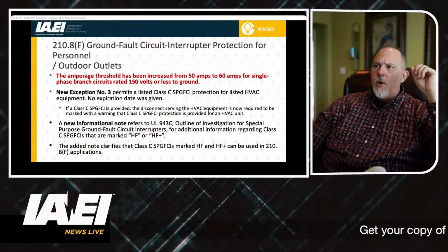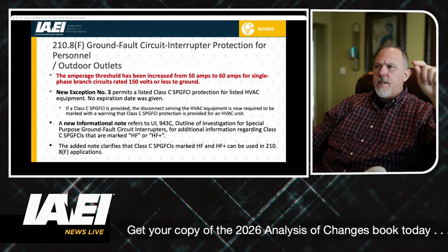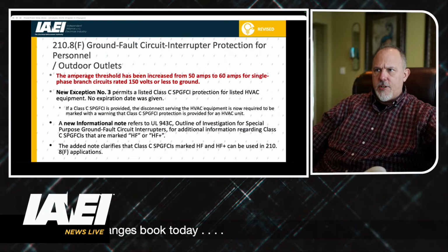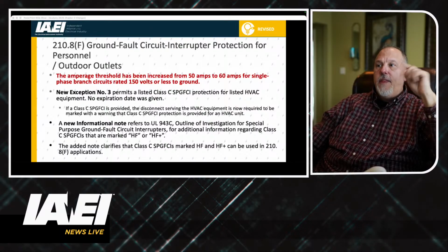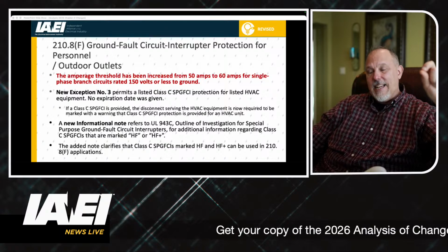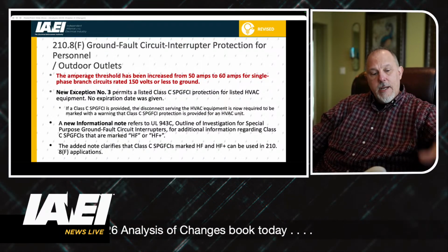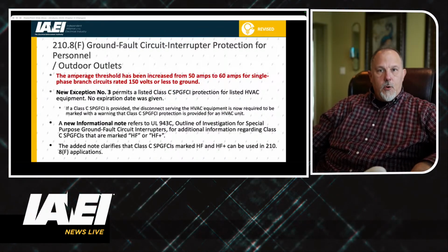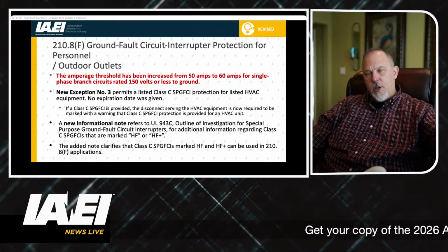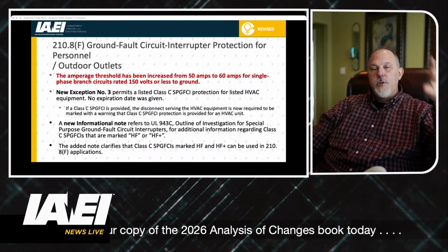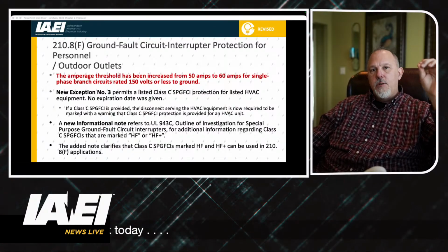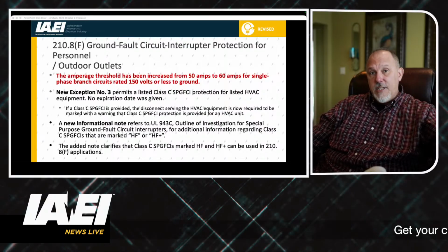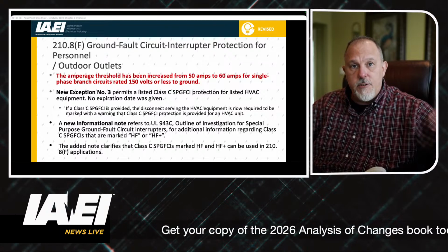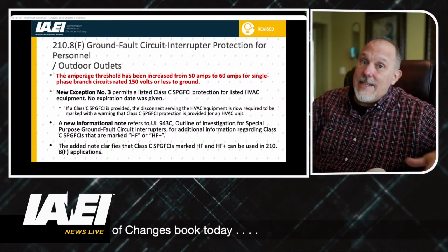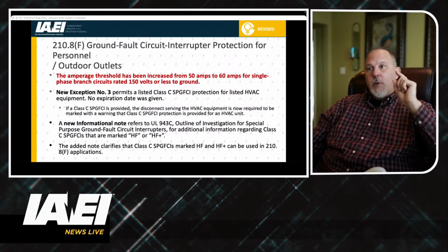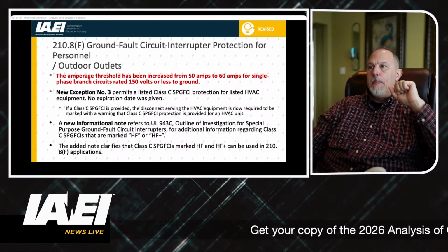Let's go back. So on 210.8F, they increased the threshold from 50 to 60 amps for a single phase branch circuit that is rated 150 volts or less to ground. They also added permission for a Class C GFCI. Now, it's called a special purpose GFCI, but Ryan Jackson is chairing a task group for the correlating committee, and the way that task group is going is to basically lose that terminology of the special purpose GFCI and simply use the terms Class C GFCI, because it's a Class C GFCI. Class A GFCI is what we know as a standard GFCI, and then there's a Class D GFCI and then a Class E GFCI. But here it is permitted to use a Class C GFCI protection for HVAC equipment.